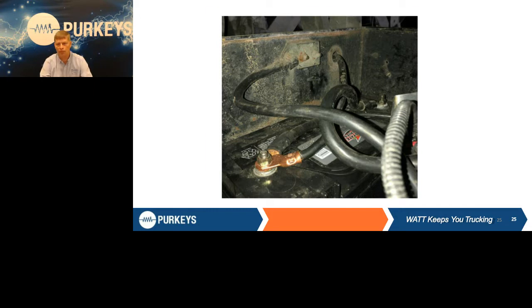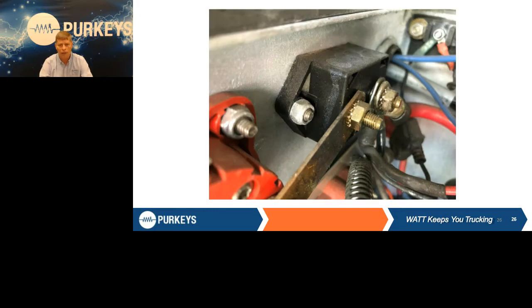Here's another one with that same type of breaker. We were out checking the charging system on it. A guy made a complaint that it's got bad batteries or something, it keeps kicking off. And it's like, well, that really doesn't have anything to do with the charging system. But let's take a look at it. And keep in mind, a circuit breaker works by heat versus just current.